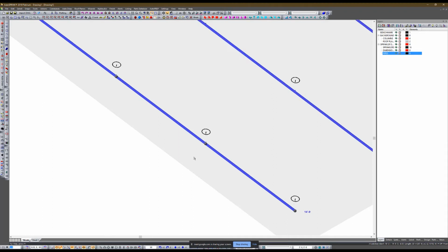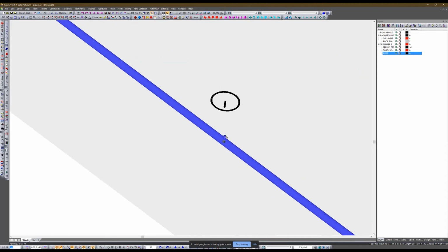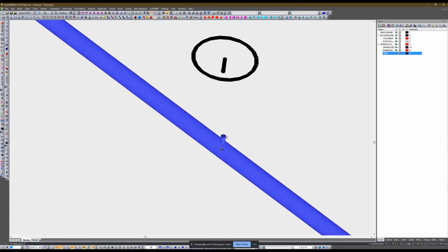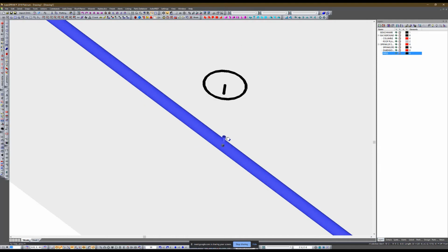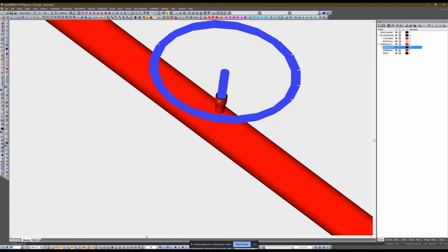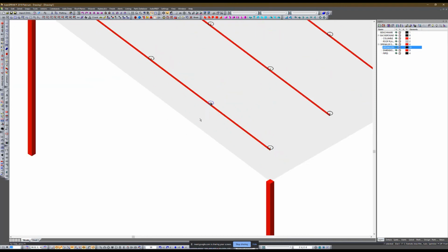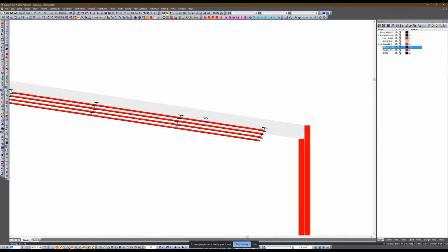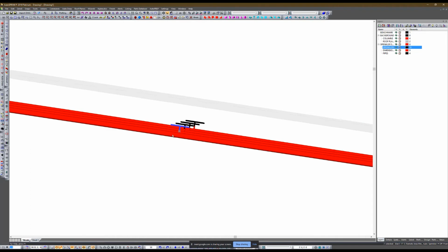Now reselect the pipe, and then at this point manually connect. So we need to click somewhere close to the end of this outlet. So now the pipe is technically lower than 1 foot below the roof plane, but the connection point on this sprinkler is at exactly 1 foot below the roof plane. So that's the process. If your sprinkler connection point elevation below roof plane is critical, that's the process that I would follow to reposition your pipe.